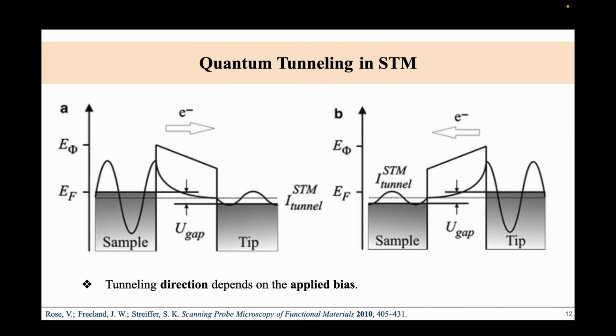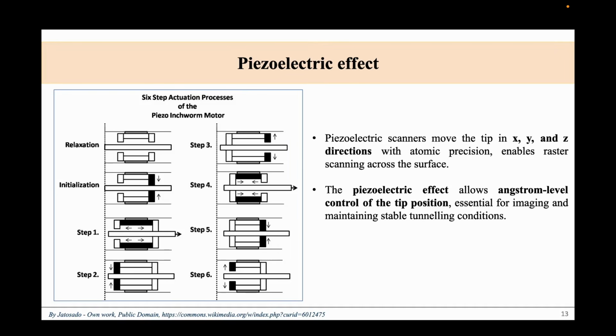Now, once we have understood how the tunneling current is produced, the next question is how we control the tip position with such high precision. To answer that, STM relies on the piezoelectric effect. The piezoelectric effect is what allows the STM tip to move in an extremely precise and controlled way. In the image, we can see a six-step actuation process of a piezo inchworm motor. This motion happens step by step in a very controlled manner. In STM, piezoelectric scanners are used to move the tip in the X, Y, and Z directions. This means the tip can scan across the surface line by line, and it can also move up and down to keep the correct distance from the sample. The key point is that this movement can be controlled with angstrom-level precision, and that level of precision is essential because tunneling changes drastically even if the tip moves a very tiny amount.